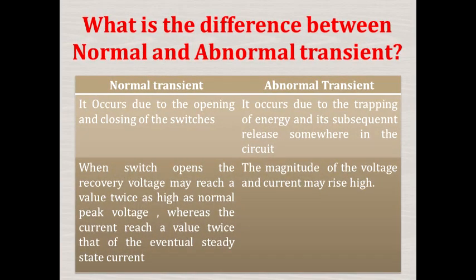What is the difference between normal and abnormal transients? Normal transients occur due to the opening and closing of switches, but abnormal transients occur due to the trapping of energy and its subsequent release somewhere in the circuit. In normal transients, when a switch opens, the recovery voltage may reach twice the normal peak voltage and the current may reach twice the eventual steady-state current, whereas in abnormal transients the magnitude of voltage and current may rise much higher.